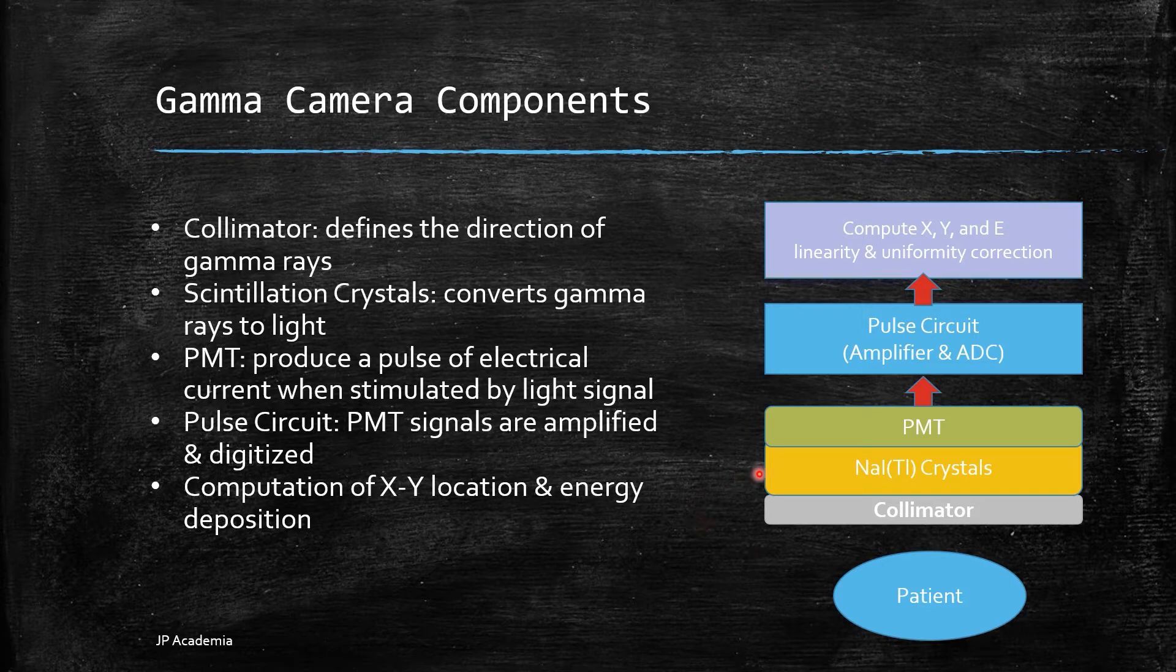The scintillation crystals, shown here in yellow, commonly made out of sodium iodide doped with thallium, converts gamma rays to light. Its main function is to absorb the gamma photons and convert it into a light image.